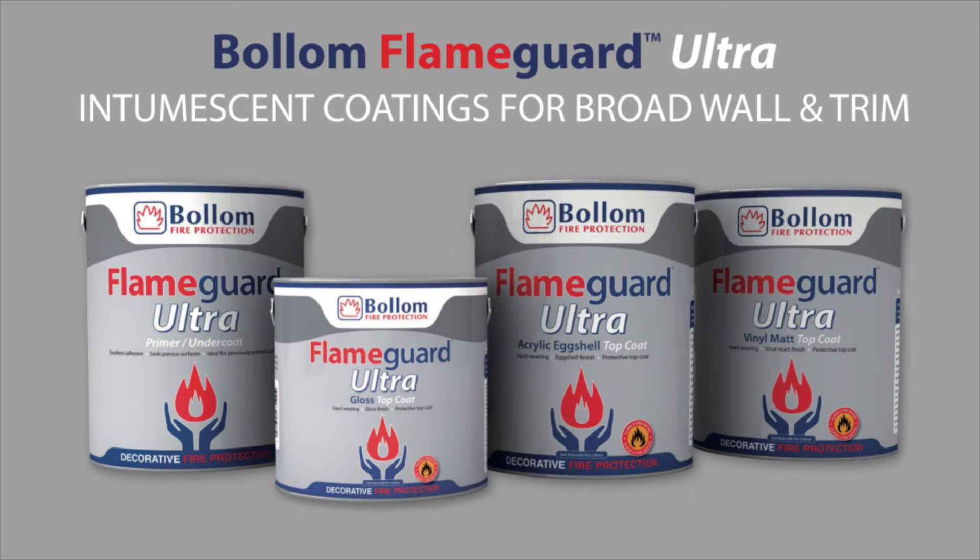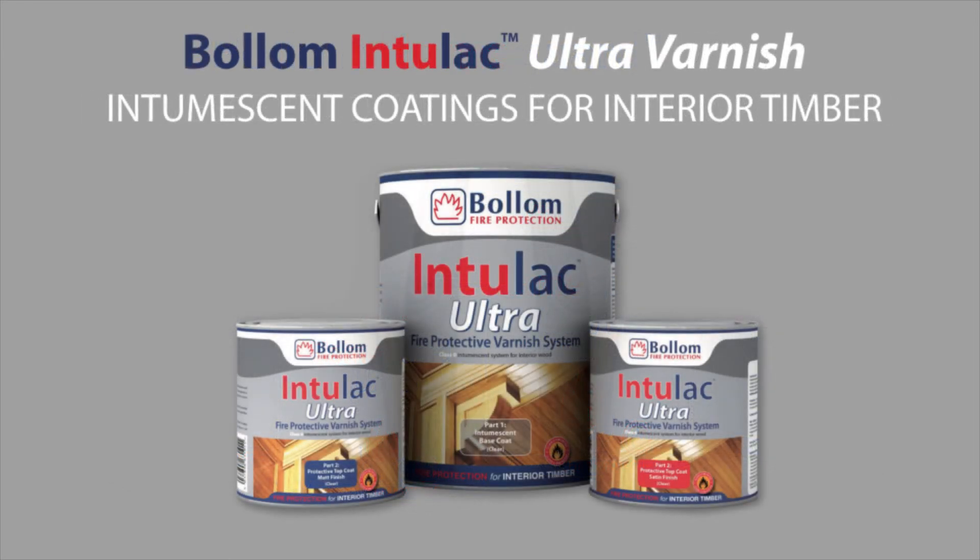It has its own proprietary primer for non-combustible surfaces and should be used over Bollom Flameguard Ultra on combustible surfaces. The single-pack Intulac Ultra Varnish system provides a high-performance Class O fire rated protective coating for interior wood surfaces in only three coats. It is available in clear matte and satin finishes.